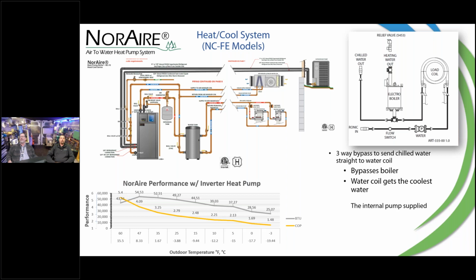I think we're going to see the rebirth of a buffer tank. Buffer tanks were kind of needed early in condensing gas boilers because they didn't have the turndown, so we used the vessel to not short cycle. Now we do have the turndown, and buffer tanks are kind of no more needed.